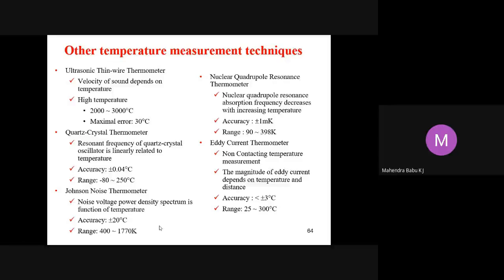Nuclear quadrupole resonance thermometer, where the absorption frequency decreases with increasing temperature, accuracy is plus or minus 1 Kelvin, range is 90 to 398 Kelvin. Eddy current thermometer, non-contacting temperature measurement, the magnitude of eddy current depends on temperature and the distance, accuracy less than plus or minus 3 degrees Celsius, and range from 25 to 300 degrees Celsius. These are the other types of temperature measurement techniques.